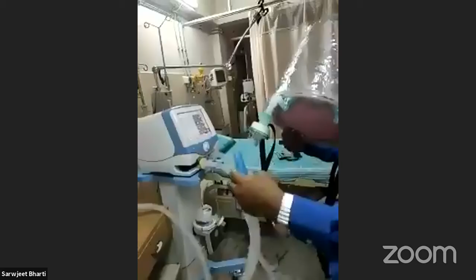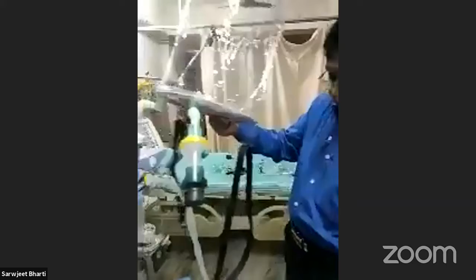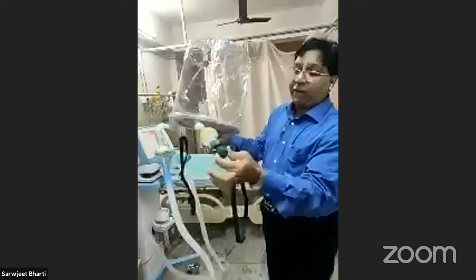So it can be used with a good ventilator, either dual limb or single limb, and this has multiple advantages. Most important is the reduced delivery of viral load to the staff who are working. Then this helmet can also be used, as I said earlier, even with ordinary machines. Look at this. This is a BiPAP machine. It just gets connected here, and the patient continuously gets positive pressure, and again the expiratory gases are taken care of by reducing viral load by adding this HEPA filter.